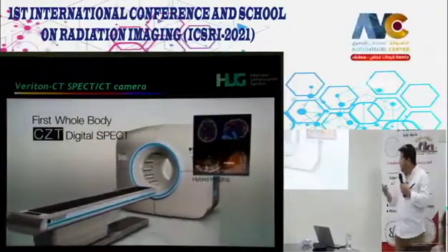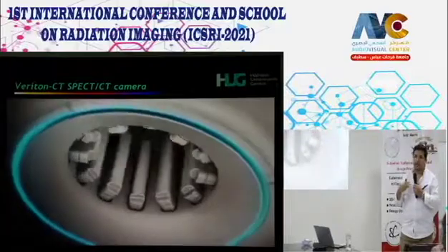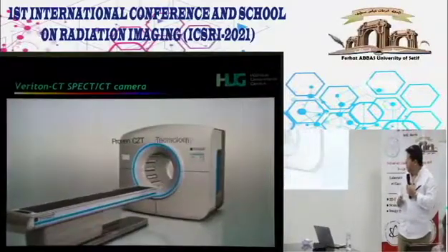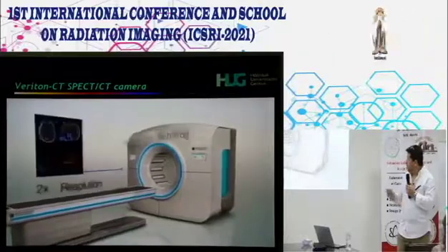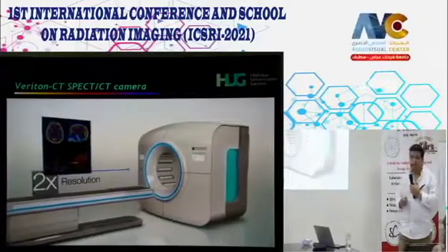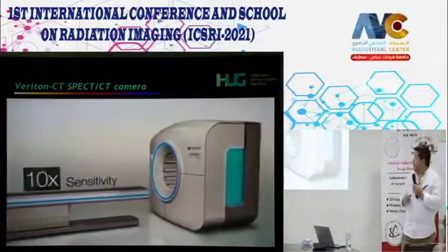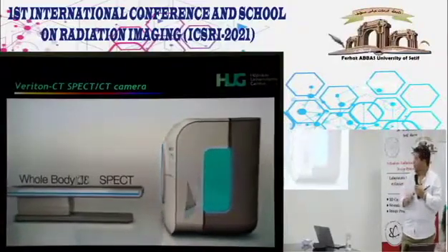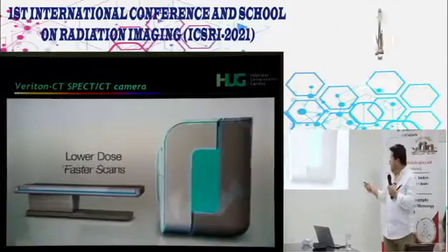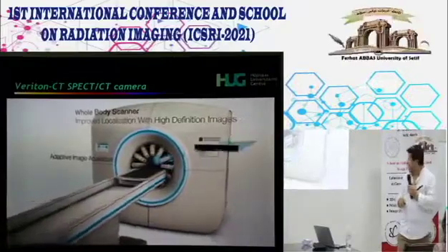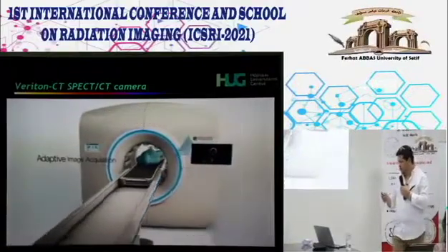The initial design was basically targeted to cardiovascular imaging, but the Veriton, which is the most recent design, uses CZT, which is a semiconductor. So there is no need for PMTs, because CZT converts the gamma rays directly to an electronic signal, and then it enables scanning extremely fast with a lower dose to the patients. So an extremely useful design.